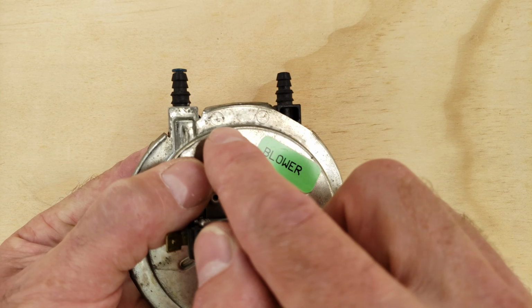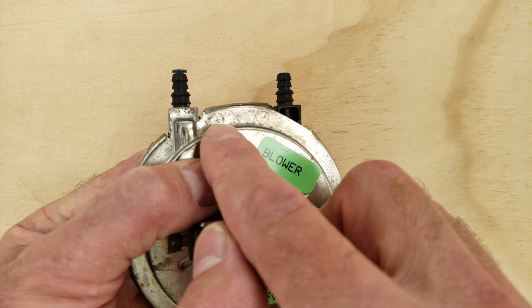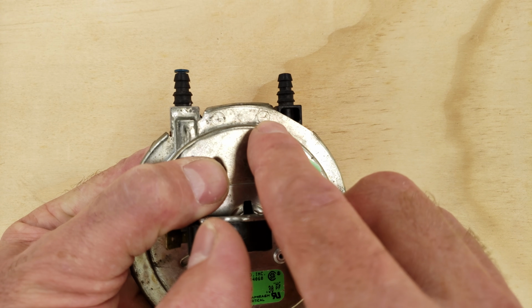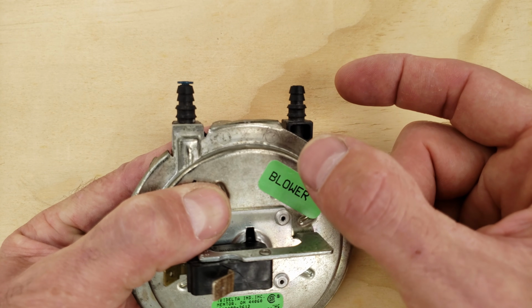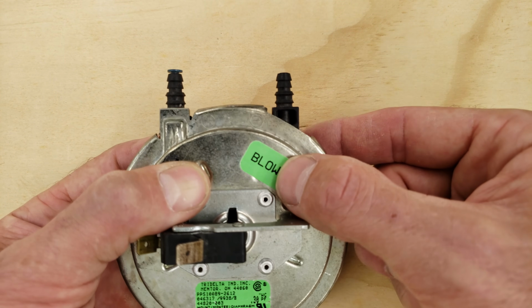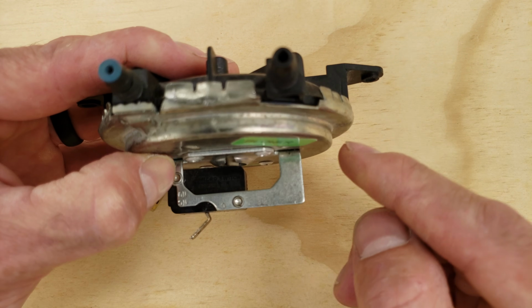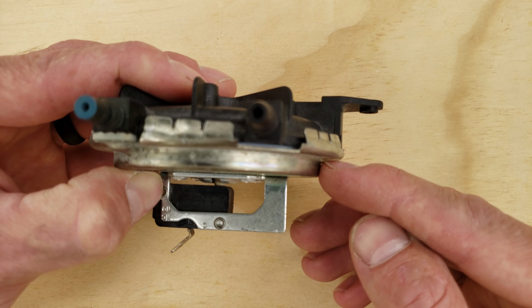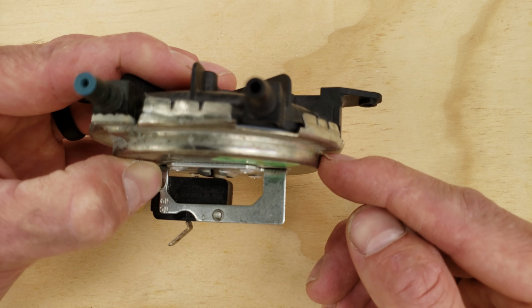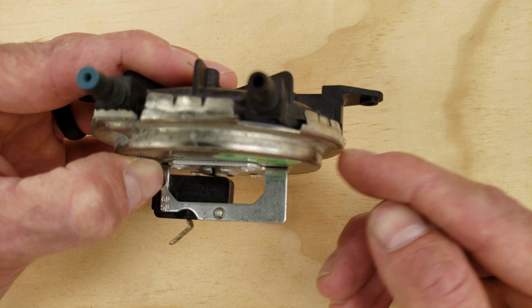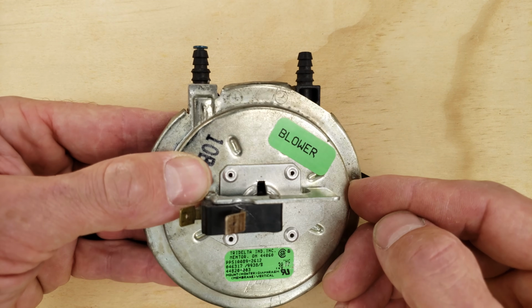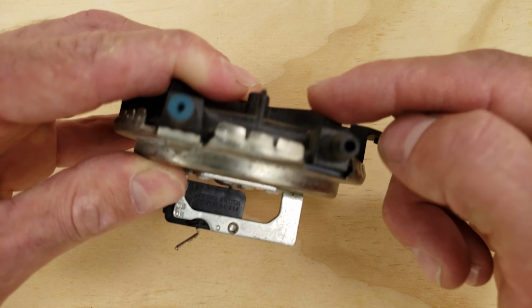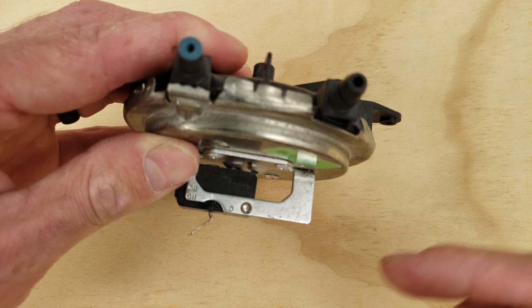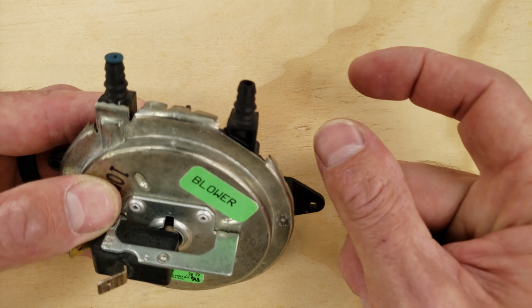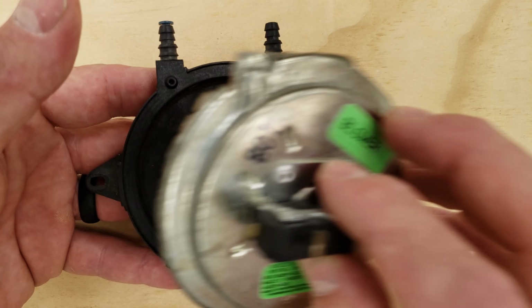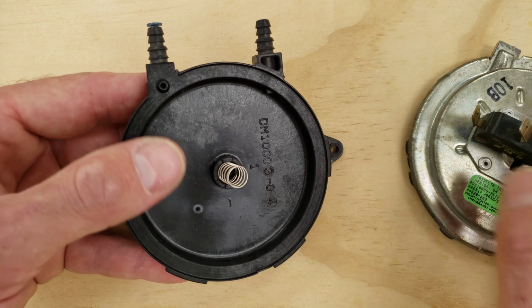And so this side is not going to get reduced as much as this side is during operation. So you still have a differential, but what I'm trying to tell you here is that there is no atmospheric pressure while the system's running. So this side is going to have a lower pressure than atmospheric pressure, but this side is going to be reduced greater than this side is. So it's going to have a differential, and that differential is going to overcome that spring pressure.